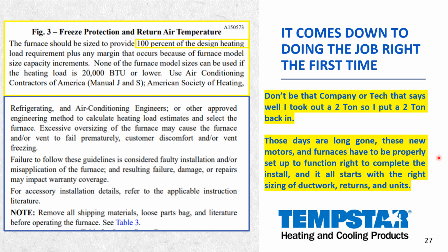And then you install this, and then you may not have 800 CFM, and you're going to get callback after callback after callback. Because what's going to happen if there's a lot of restriction, you're going to have a blower motor go out in maybe the first year, maybe 2 years, it might make it. You're going to have loud compressors, rattling compressors, or a compressor that'll go out on you, and you'll need to know why that is. The days of taking out a 2-ton and putting a 2-ton back in, those days are long gone. With the new motors and furnaces, they have to be properly set up and function right to complete the install.